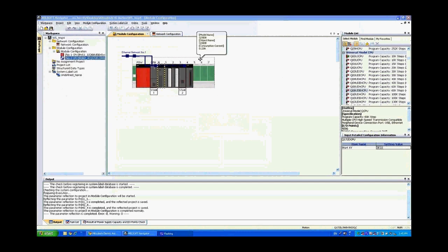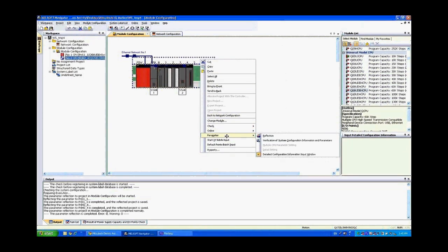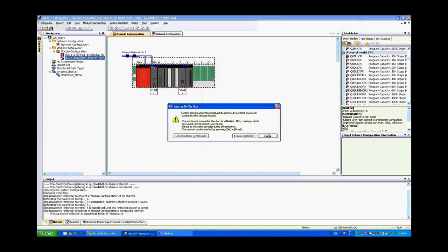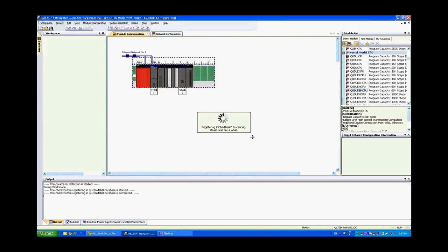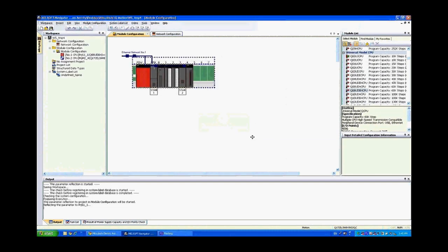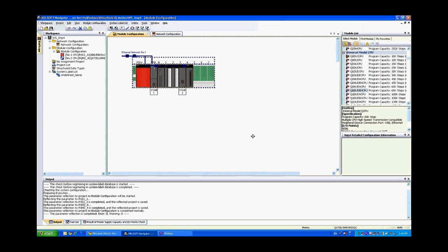Now we're going to reflect all the parameters to the controllers. Go ahead and go to parameter and reflection. This will send all of the parameters from the PLC and the motion controller down into their respective modules and make sure that there are no conflicts between both controllers and the memory sharing that takes place between them. So down here you'll see the error zero warning zero.